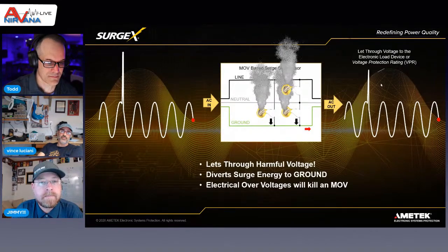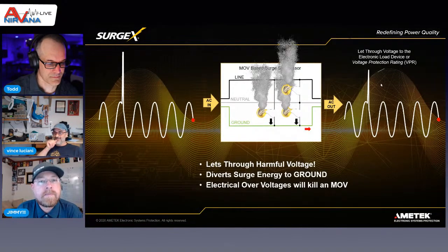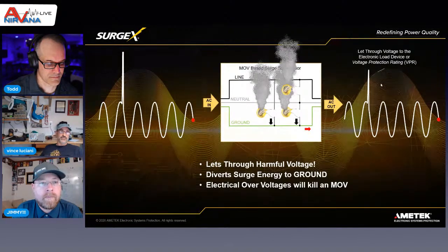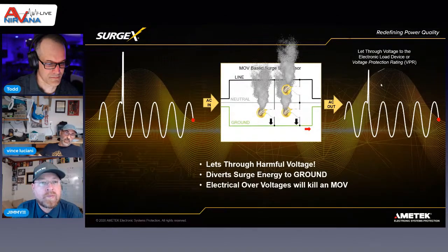One detriment to the way some MOV-based surge protectors are set up is that they utilize that ground bus as a place to dump this surge energy. The problem is that when that surge energy gets dumped into ground, depending on how the load equipment is designed, there's a possibility for that surge energy to go into that load and cause a lockup.